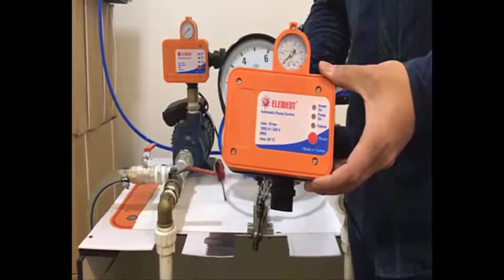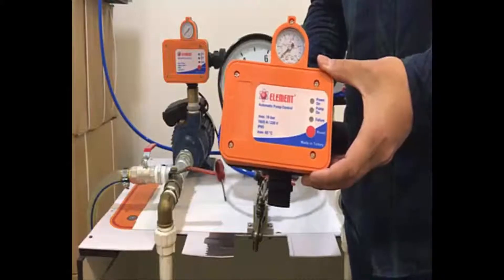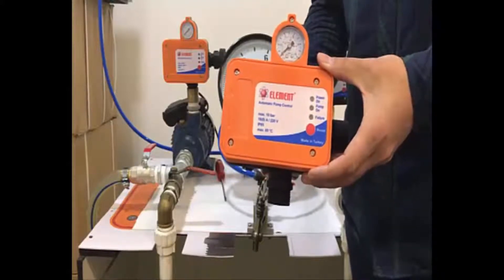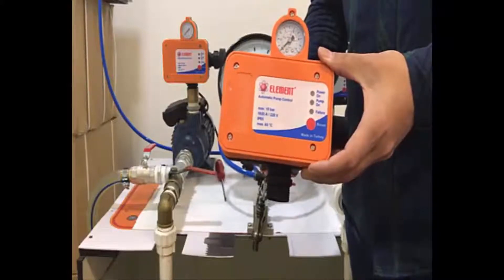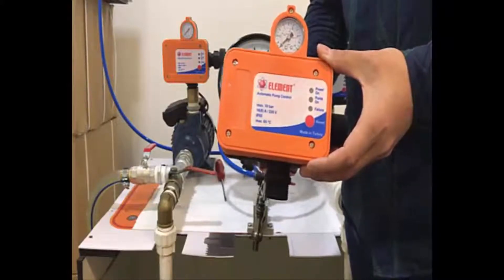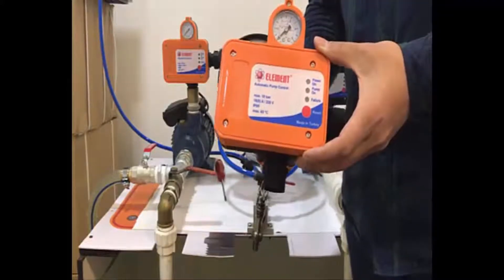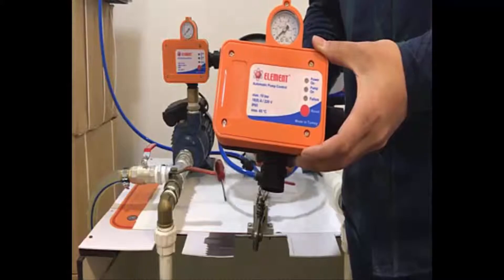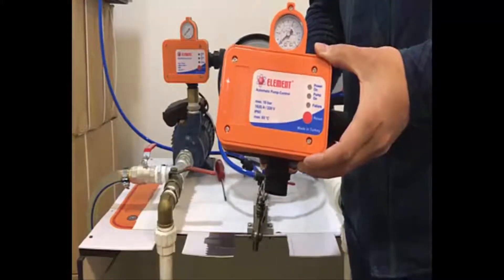Our device is controlled by an electronic card. This device can control the pressure of the water in the system and also protect the pump engine from being damaged in case there is no water in the tank, the city water is cut off, or from any other unexpected reasons. The device can control the restart pressure of the pump between one bar and four bars.